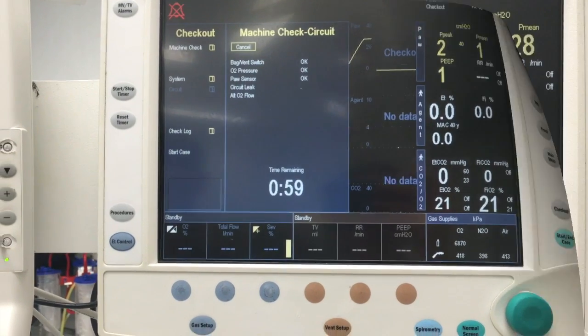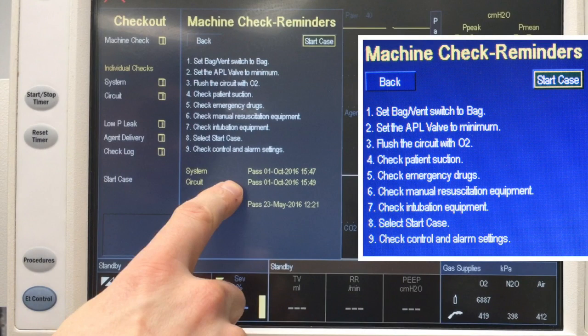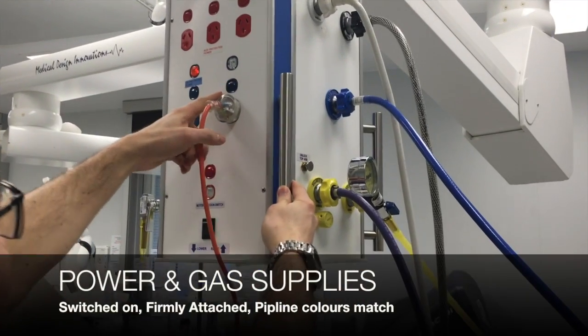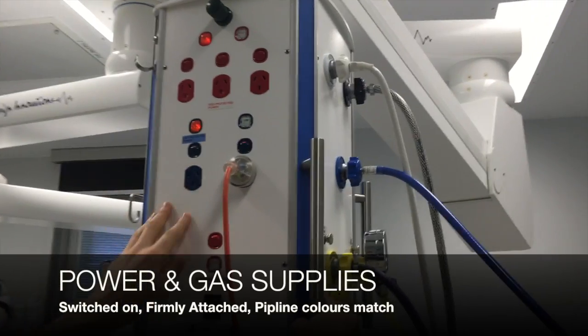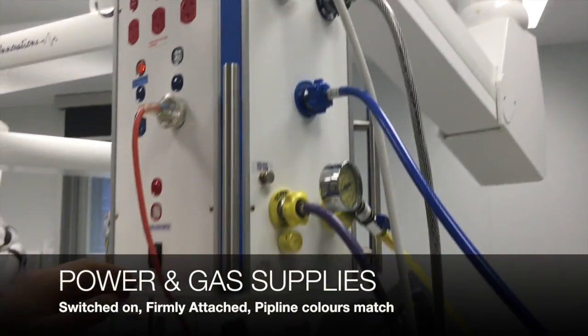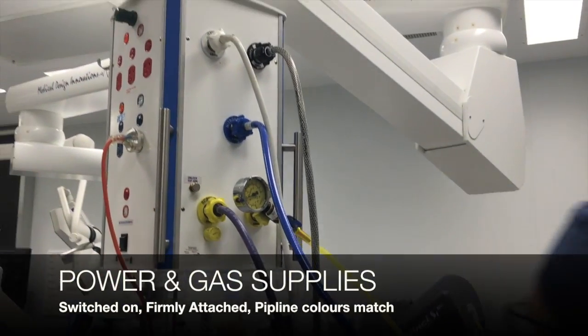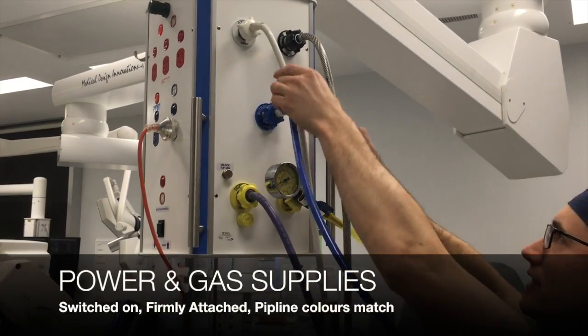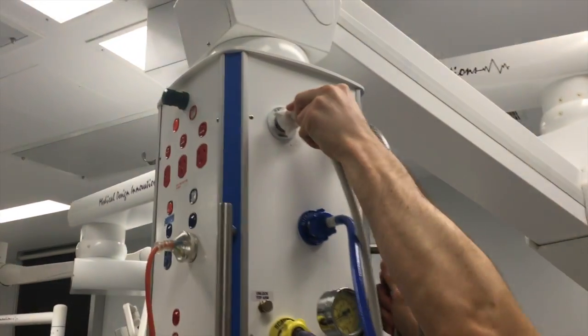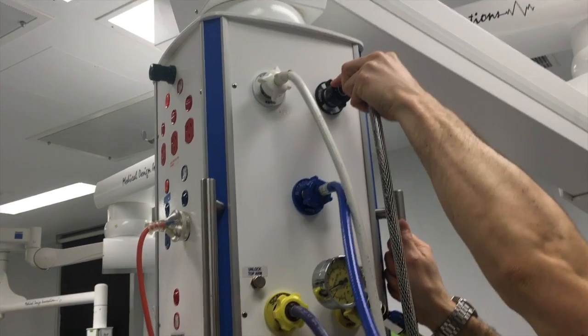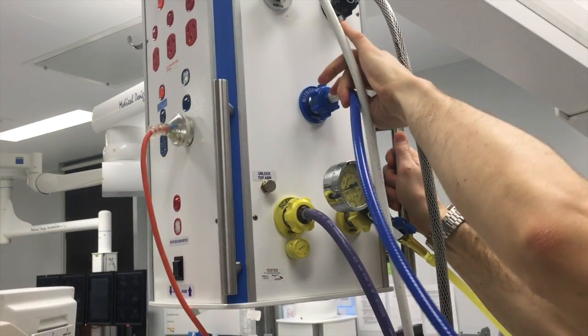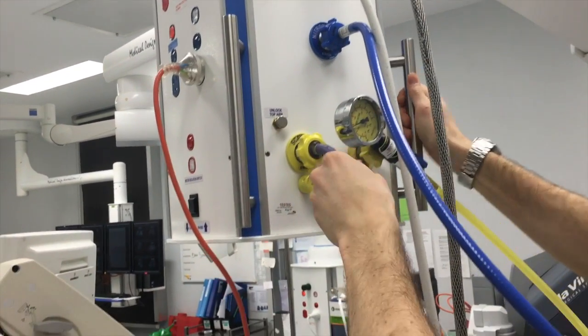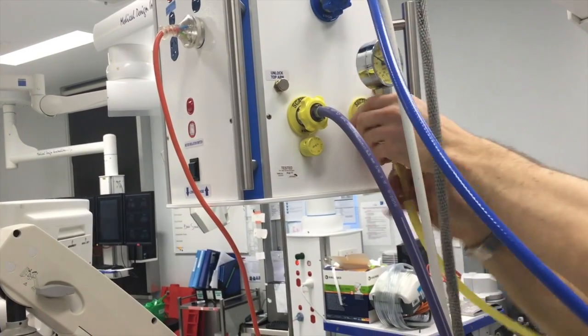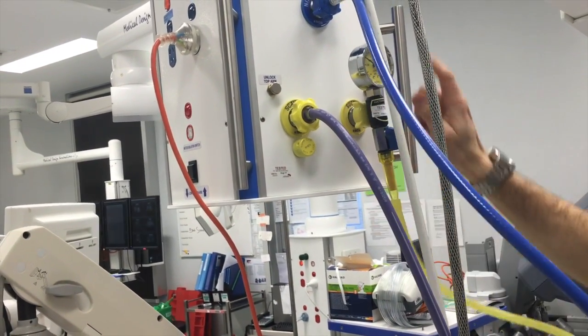Once this is complete, the machine displays a final checklist of reminders to do next. Following the AAGBI guidelines, the next things to check is that the power supply is plugged in and switched on. This might seem like a redundant step, but actually the machine can run purely on its own battery supply, only to run flat when you least expect. It's also important to check that the gas pipelines are firmly and correctly attached. We will cover checking the oxygen supply later in more detail.